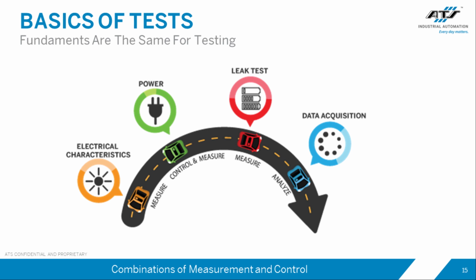We've got leak tests. The leak tests vary tremendously in terms of technologies people deploy, based on the leak rates we're looking for and the size. The large electrical packs are very challenging due to the large volume enclosed. And then of course the data acquisition system for collecting this data and analyzing it, making the pass-fail kind of considerations at the end.